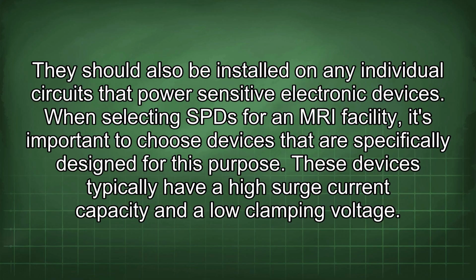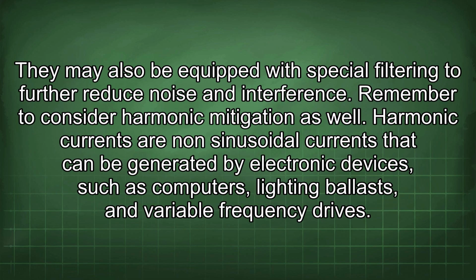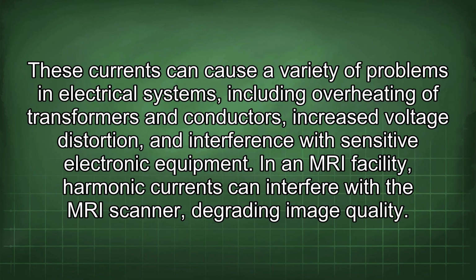When selecting SPDs for an MRI facility, it's important to choose devices that are specifically designed for this purpose. These devices typically have a high surge current capacity and a low clamping voltage. They may also be equipped with special filtering to further reduce noise and interference. Remember to consider harmonic mitigation as well. Harmonic currents are non-sinusoidal currents that can be generated by electronic devices such as computers, lighting ballasts, and variable frequency drives. These currents can cause a variety of problems in electrical systems, including overheating of transformers and conductors, increased voltage distortion, and interference with sensitive electronic equipment.